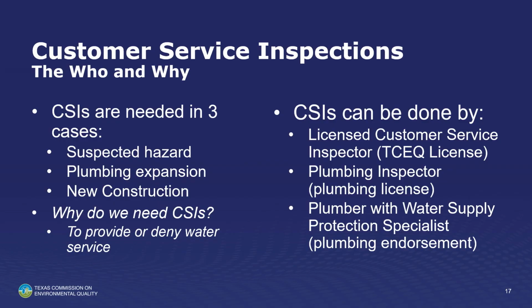Let's talk a little bit about customer service inspections. CSIs are needed in 3 cases: suspected hazard, plumbing expansion, and anytime we have a new construction. They absolutely are needed. And so who can do a CSI? Well, if we're licensed by TCEQ, we can do a CSI. That's what you're going to see most of the time.